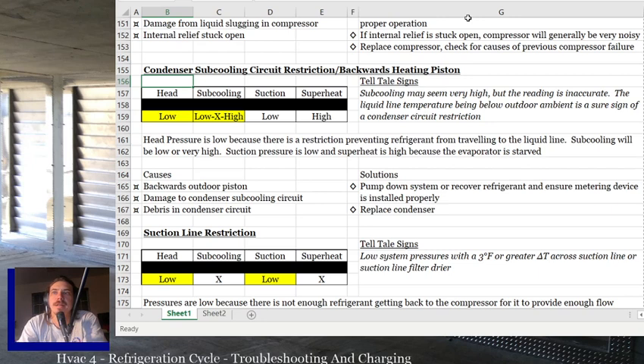The telltale sign is subcooling may seem very high, but the reading's inaccurate. It doesn't mean anything. Your sign isn't even related to the subcooling, but it kind of is. It's the liquid line temperature being below outdoor ambient that is your telltale sign. Remember we talked about this, that liquid line temperature cannot be below outdoor ambient temperature. So if it's 80 degrees outside, that liquid line cannot be 70 degrees. Can't happen. It's not possible.